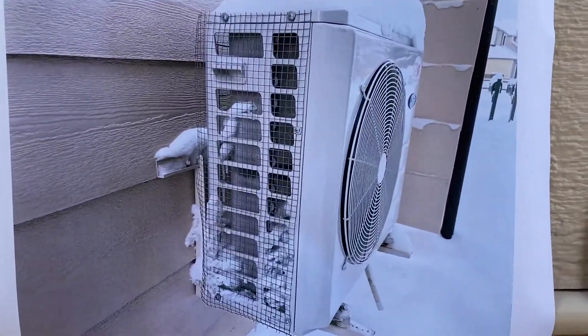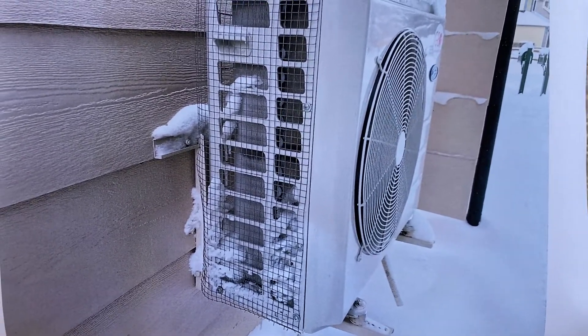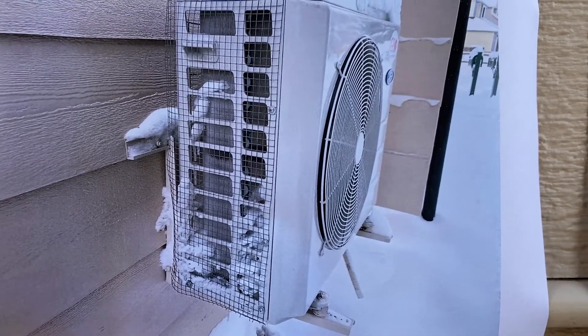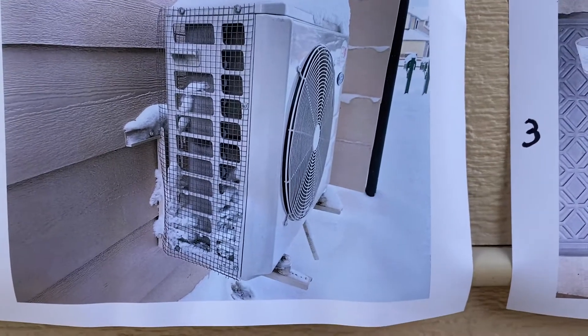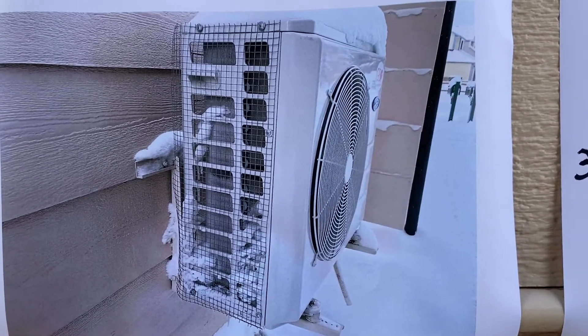This compressor had snow buildup. There is a sensor in there that will reverse and heat up the coils to keep it somewhat melted — that happens about once an hour. But what if we could delay this self-melting phase, possibly permanently?